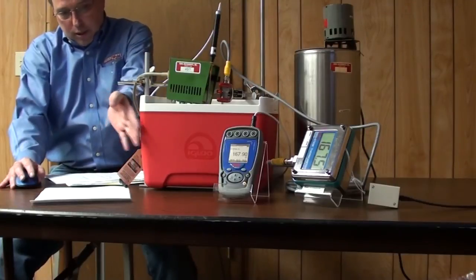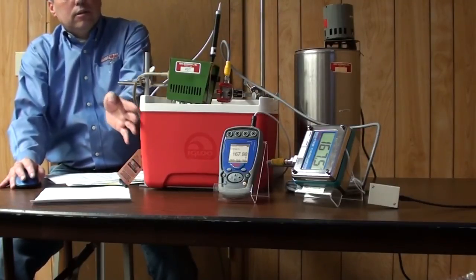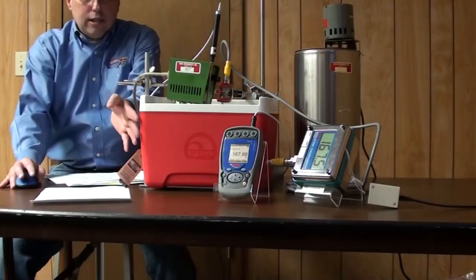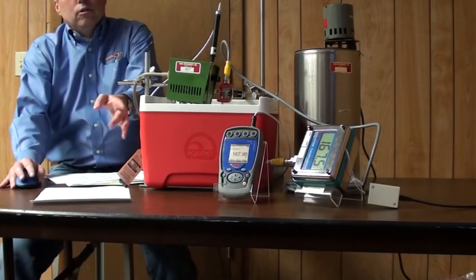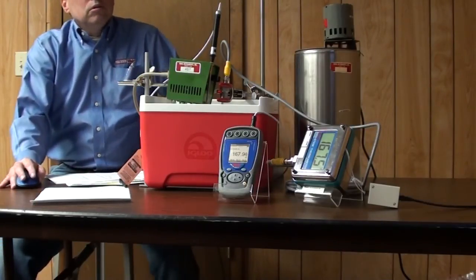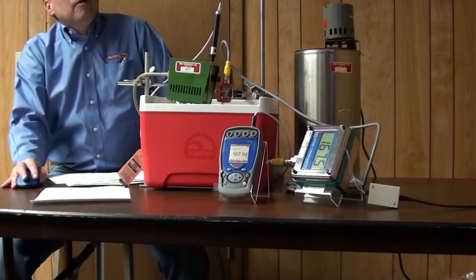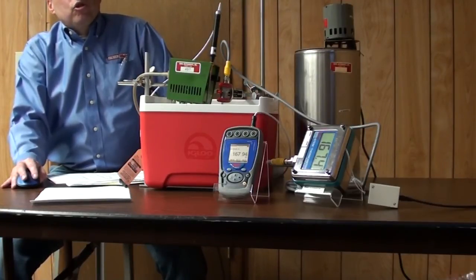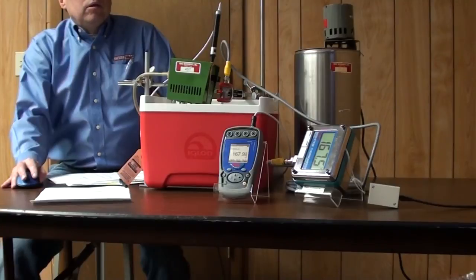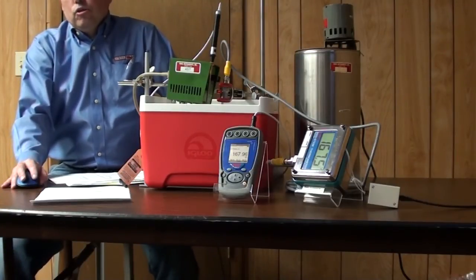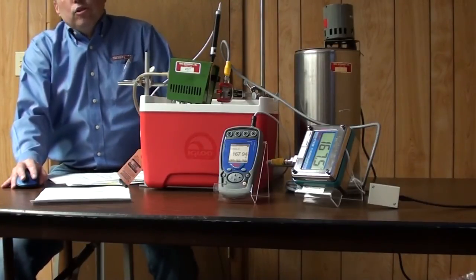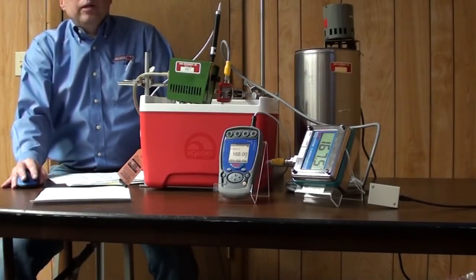In this case, it's a hot water bath. I did not bring any of our high temperature oil baths in here, so I'm just using this portable hot water bath. But we have our source temperature, so this is the nominal. If we were processing and we used 230, 240, and 250 temperatures, we might want to test it at all three of those temperatures. Those would be our nominal.